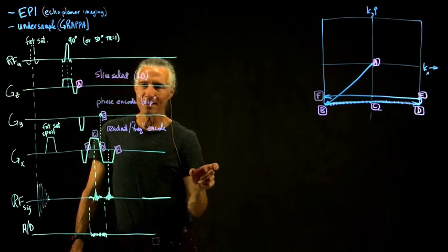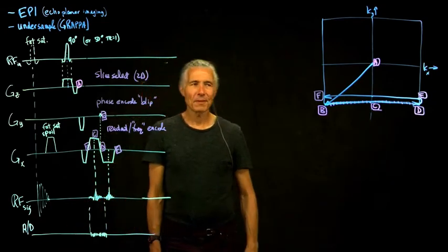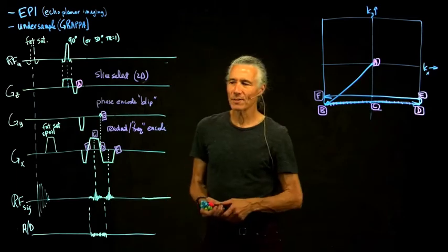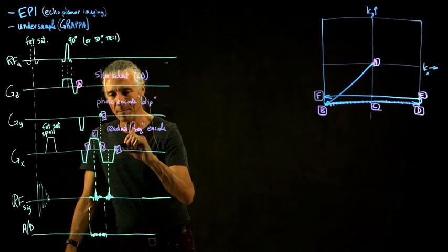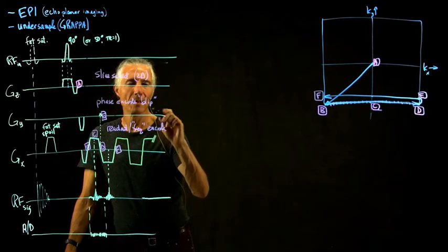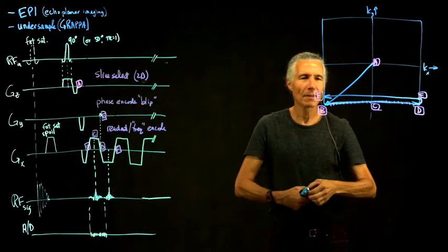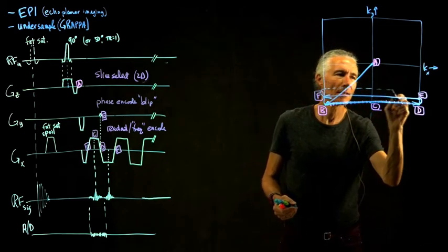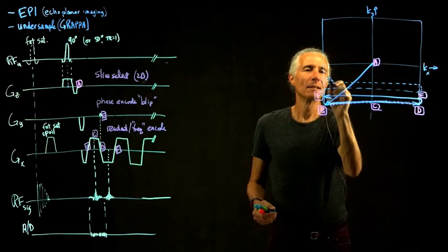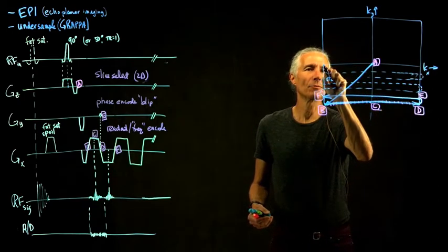If you look on the scanner, it says TE, time of echo. So what does that mean? Say it says 32 millisecond echo. You've got all these echoes. What it means is the time to when you get through the center of K-space. The gradients will rapidly go back and forth like this for a long time, like 32 times. Another blip occurs here, we go across here, another blip occurs there, go across here, etc. I'm not drawing as many as there are. Eventually we get up here and we actually go through the center of K-space.